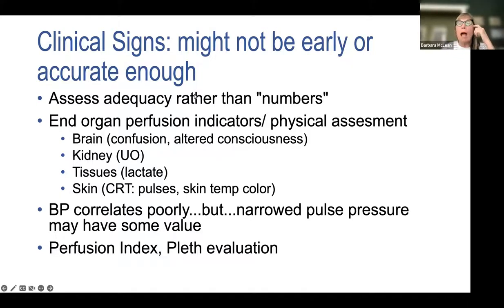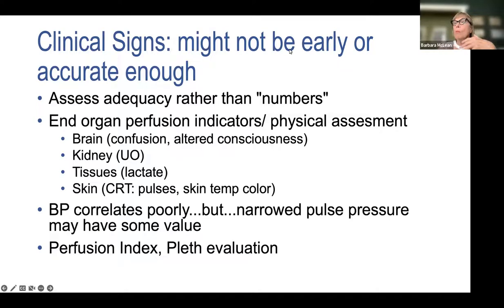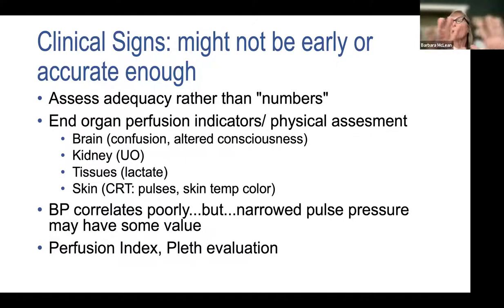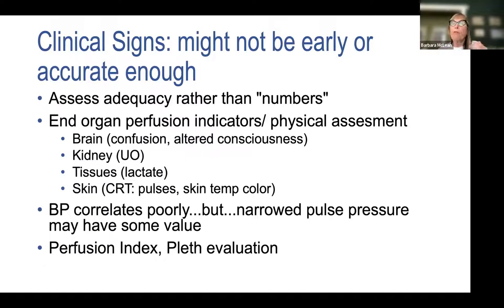Continuous monitoring of arterial pressure lets us look at continuous pulse pressure correlating with stroke volume. Another tool already embedded in your monitor is the perfusion index — called 'PERF' on Philips monitors and 'PI' with Masimo technology. This correlates to the plethysmographic waveform of your pulse oximeter and provides a non-invasive measurement of pulsatile perfusion quality, without requiring any extra equipment.